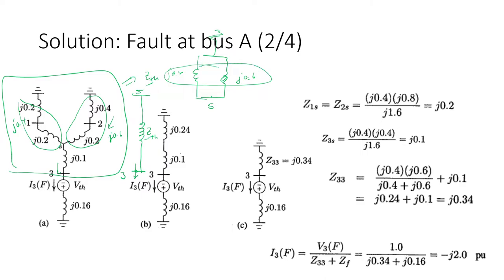These two are connected to share the same voltage, so they are in parallel. So the equivalent of these two becomes 0.4 times 0.6 divided by 1. 0.4 times 0.6 becomes 0.24, with the two decimals, that's why we have 0.24 per unit. So this is 0.24 per unit from the ground up to point S, which is this one here.